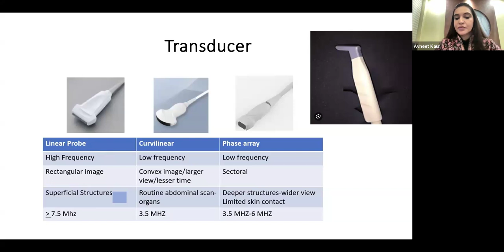Curvilinear probes again have a lower frequency. They are convex, they acquire a convex image, and they have a larger footprint. They are routinely used for our abdominal ultrasound, and they use a frequency of approximately 3.5 to 8 MHz. Phased array probes have a smaller footprint. They give a sectoral view and are typically of lower frequency. They help to detect deeper structures, with a smaller footprint. So they are good for deeper structures and smaller babies where we need less area for our image acquisition, and they use frequencies anywhere from 3.5, going up to 10 to 12 MHz as well.